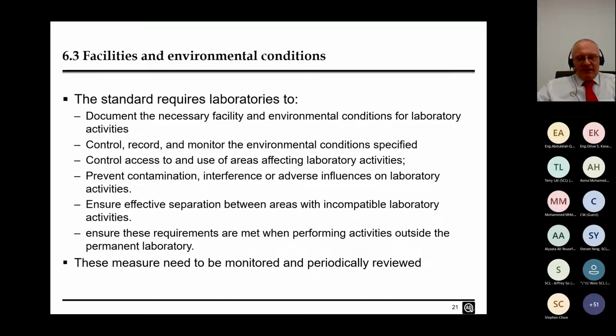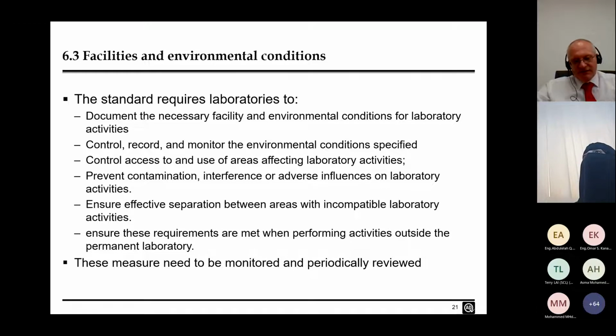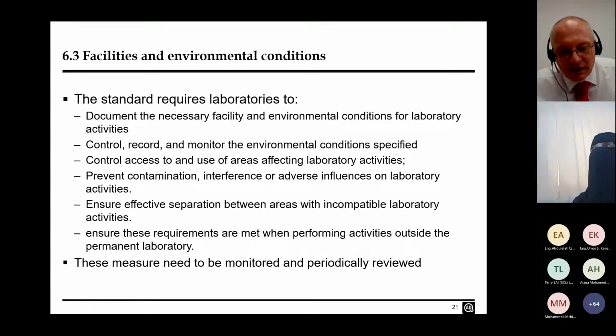This needs to be monitored and periodically reviewed. So the fact that you've set up your environmental conditions or your access control once when you moved into the laboratory is not enough. As well as monitoring what's going on, you need to periodically review the access control, review the environmental specifications. Do they need to be changed? Do they need to be made tighter? Do they need to be made broader? So these things have to be monitored and periodically reviewed. It's not a do it once and then forget about it.